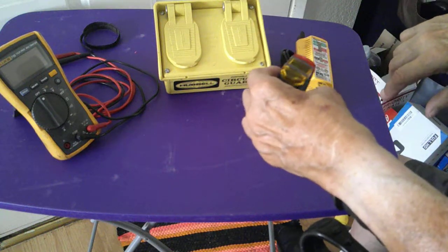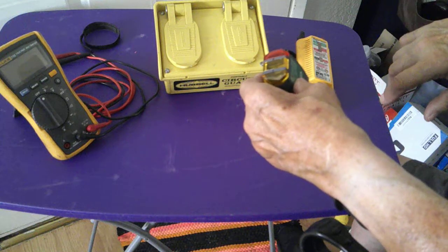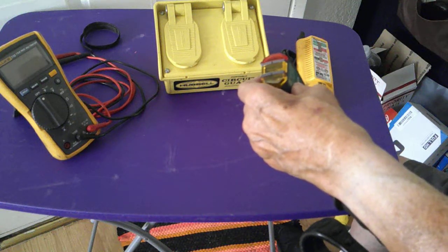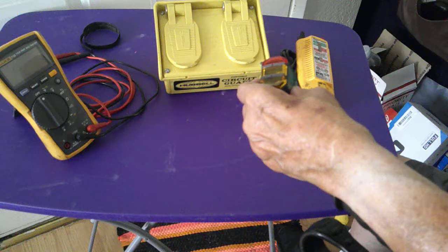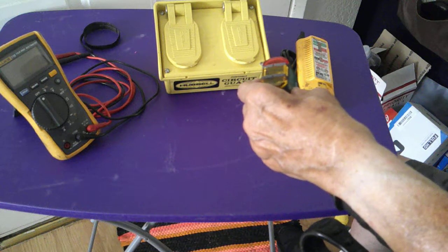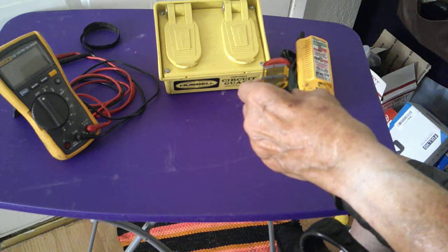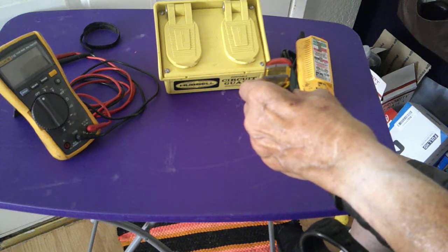Now this is very helpful when you're testing and troubleshooting circuits in a residential application, even in a commercial application, because this will tell you whether or not you've got a switched ground, or a switched neutral, or a switched hot, or anything like that.